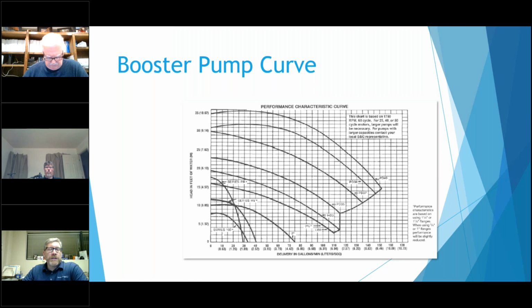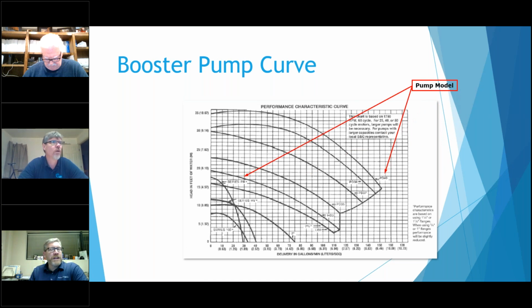So we'll run through some of these pump curves. This is just the booster pump curve. They're all somewhat very similar, but a little bit different once you get to the larger ones as far as the information on the pump curves. This one here is pretty simplistic on the booster pump curves. You got your model numbers. There's a PD40 down to an LD3, a 2-inch booster, Series 100. But basically, each pump is one pump curve.